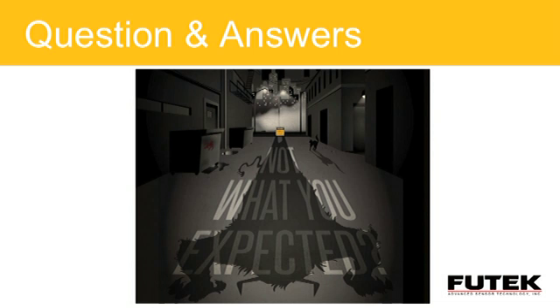One thing we do here at FUTEK is have interim checks of our reference equipment. We don't wait for the 1 year calibration; every 3 months at maximum we go through and make sure the product is performing the way it should. You could take that advice on your side too, have some basic weight where, if you can, check it to make sure it's still within those parameters and getting the results you want. Because the worst thing that can happen is after 1 year, if you send it back for calibration and it's outside of your requirements, it creates a lot of headache and extra work if you find out something happened to your sensor between calibration intervals.